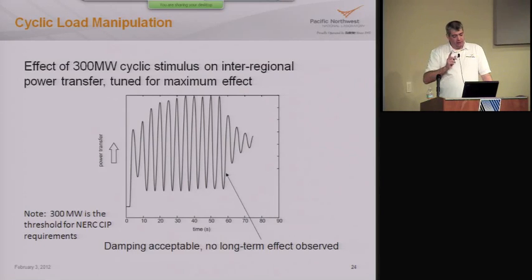So then we tried something different. In the Western power grid, there are some oscillatory dynamics you can exploit. We looked at whether we could cyclically shed and reconnect load to try to stir up one of these lightly damped oscillations. For this one, we picked 300 megawatts as our control actuator.